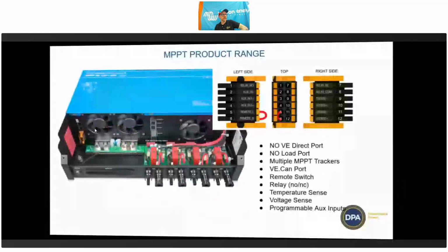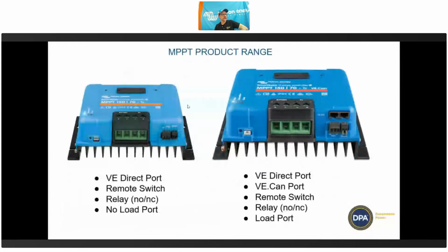So that's the range. I'll just explain one more time so people understand how to size the array. The first value determines the voltage that you can put into it. So that's your string voltage. If you've got a big system, unless you want to run them in parallel and have large current coming off the roof, you normally want to run a pretty high string voltage, so you can just have one pair of cables coming down off the roof. But the second value is the current output, and that is going to determine the size of the array that you can install.